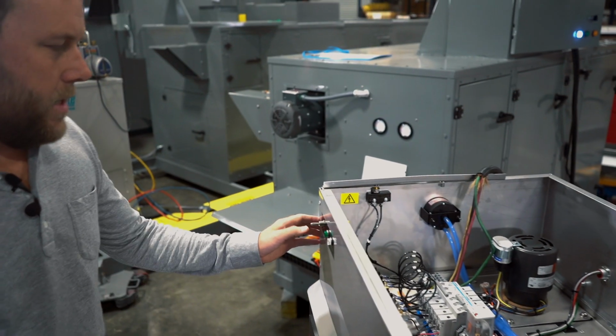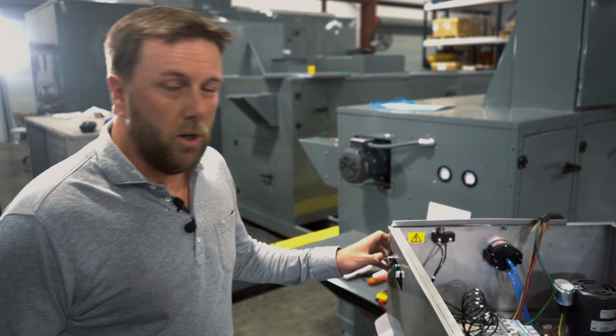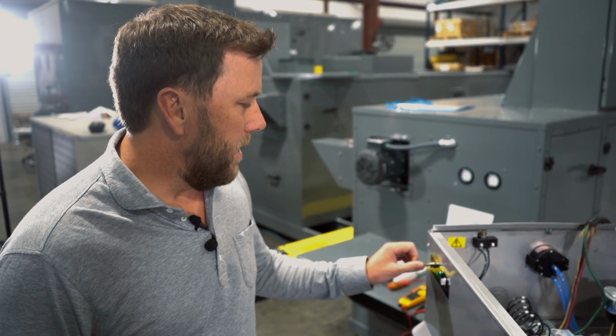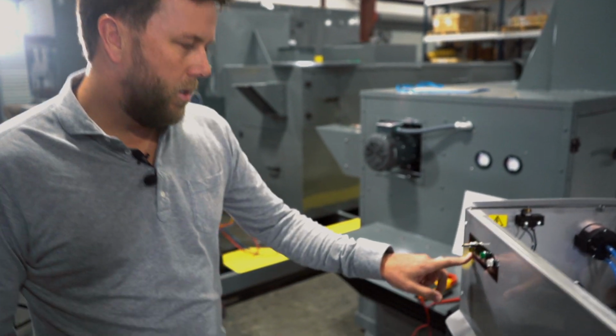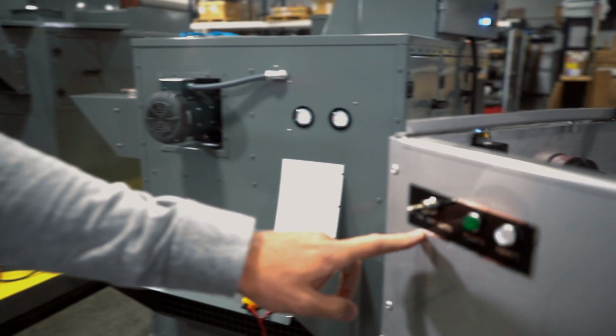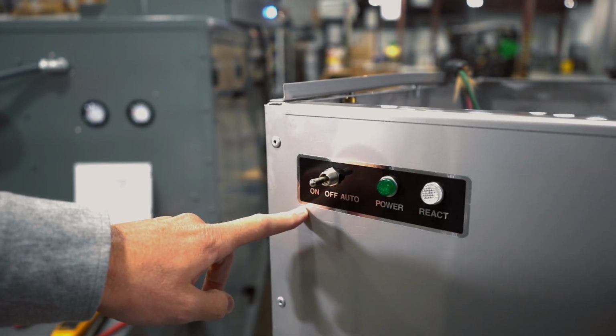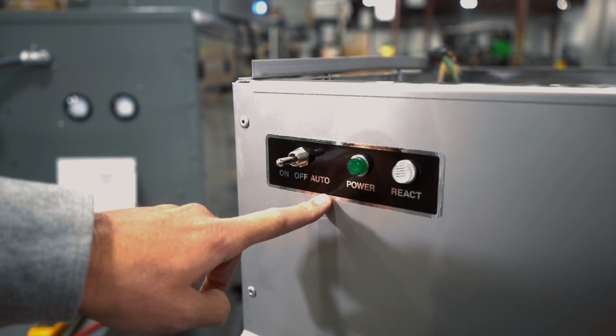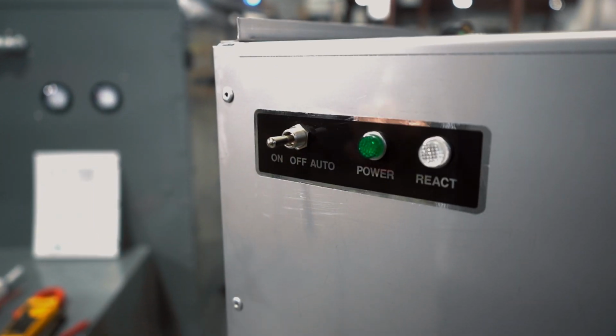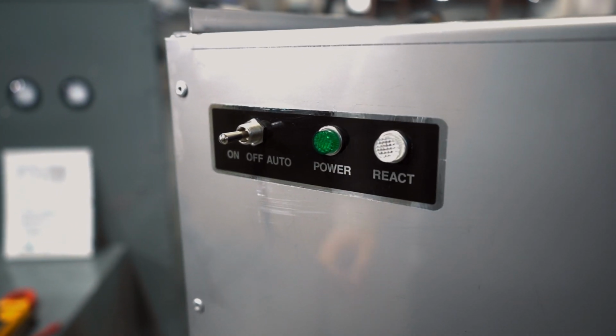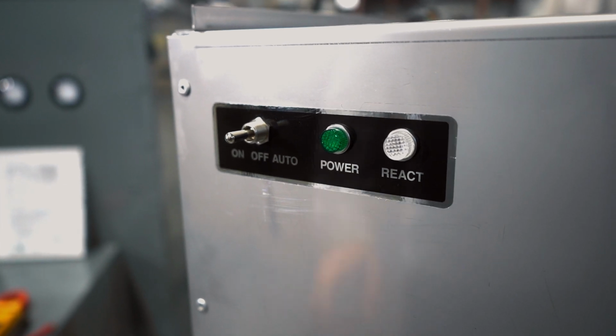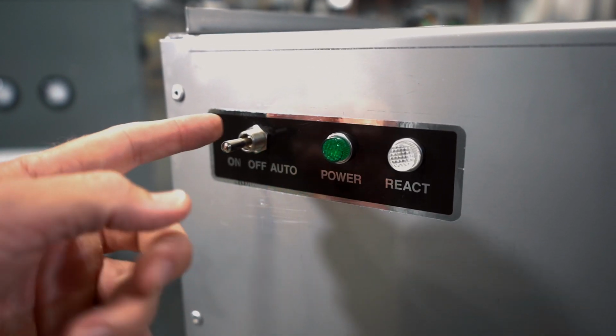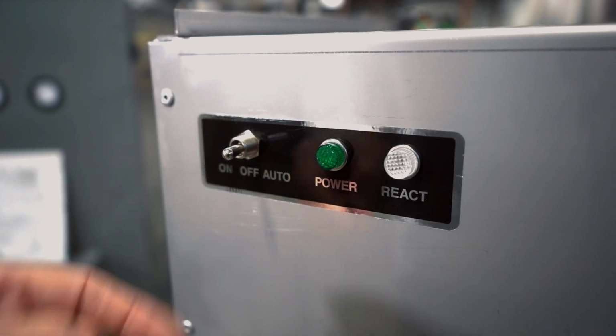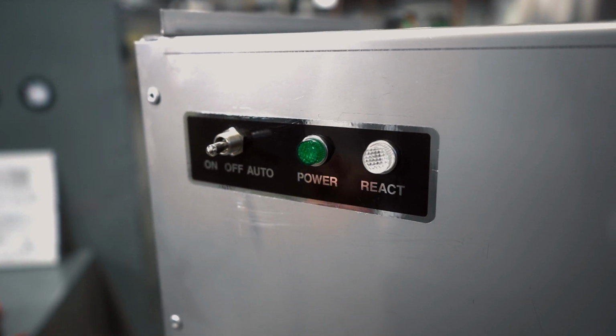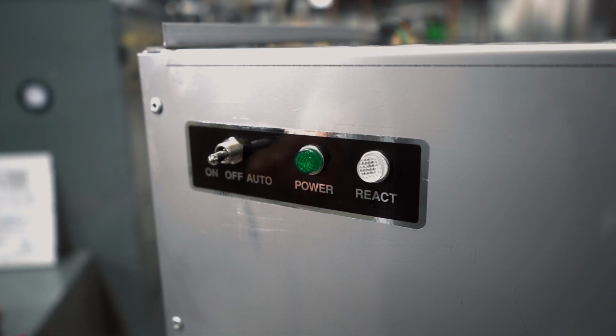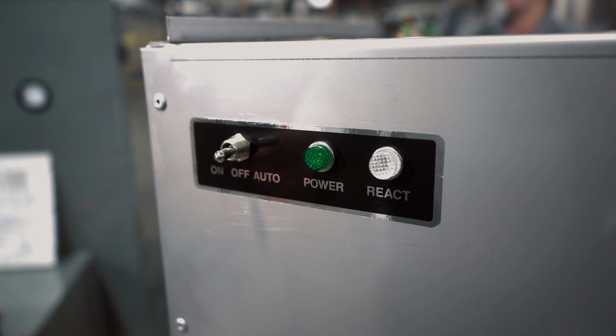Now that we have the 2-pole and the single pole breakers on, we can initiate power to the system, which we will do by turning this 3-position switch to the on position. If I was to turn it to the auto position, we need to have an external run relay or an external run command from the customer. If I turned it to auto right now, nothing would happen due to the fact that I do not have a run command from the customer.